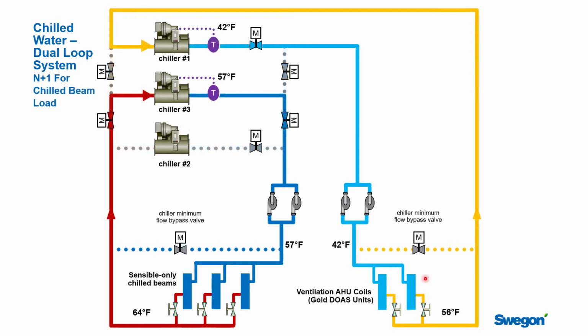And then of course, what if it went the other way, where we need to take this chiller off for service? We could again use our crossover chiller, reset its chilled water supply temperature from 42 to 57, and then switch the valving to allow it to service the chill beam. So if you have a large enough system that you want to consider running 2 separate loops, but you are looking at how you can share chillers and equipment so that you can get some kind of redundancy or resiliency built into the chiller plant, this is a good approach to allow you to mix and match chillers to share the load out. And that way, if you have an issue on one loop, you're not going to completely shut that loop down.